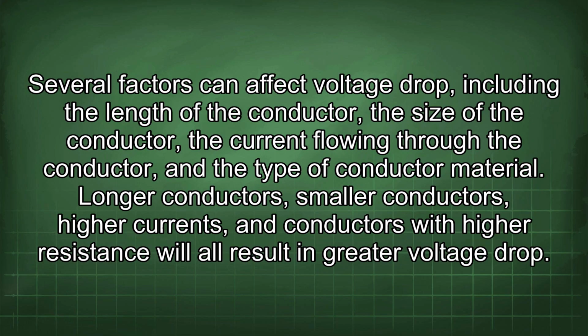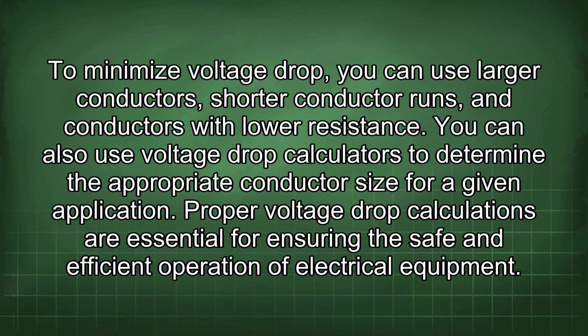Several factors can affect voltage drop, including the length of the conductor, the size of the conductor, the current flowing through the conductor, and the type of conductor material. Longer conductors, smaller conductors, higher currents, and conductors with higher resistance will all result in greater voltage drop. To minimize voltage drop, you can use larger conductors, shorter conductor runs, and conductors with low resistance. You can also use voltage drop calculators to determine the appropriate conductor size for a given application. Proper voltage drop calculations are essential for ensuring the safe and efficient operation of electrical equipment.